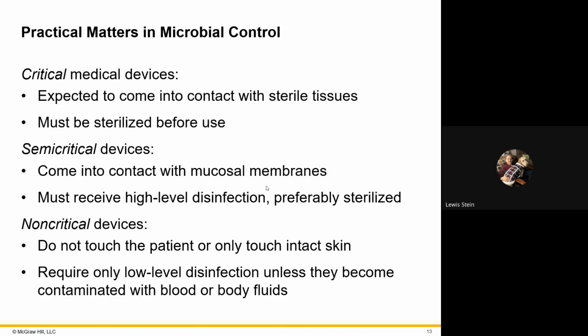That's changed a little bit because now the manufacturer typically uses something like a suitcase that you put hydrogen peroxide in that will sterilize it. The reason I'm bringing this to your attention, years ago there was a big problem. If you did not know, these tools are basically fiber optics that you look through, the way that we would look at the interior of a knee, which has to be, the tip has to be sterile if you're doing arthroscopy or something like that.